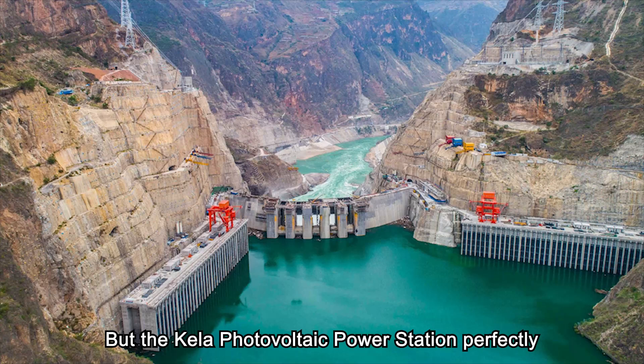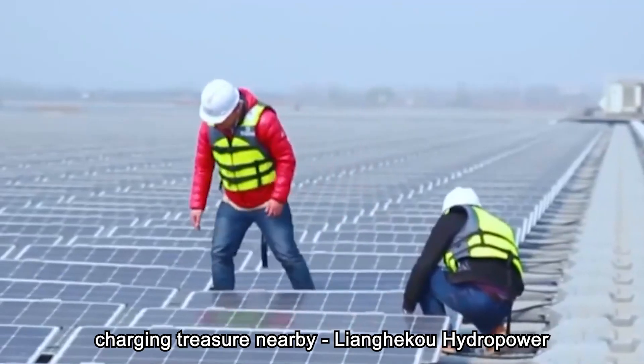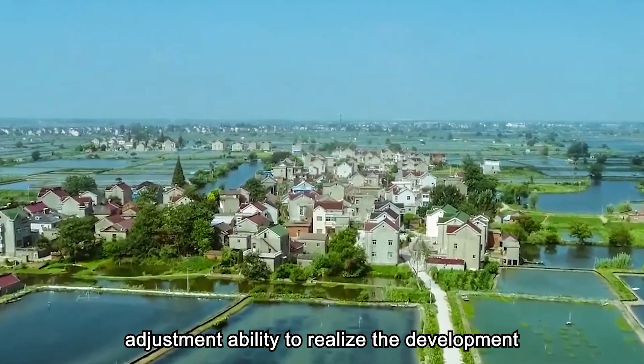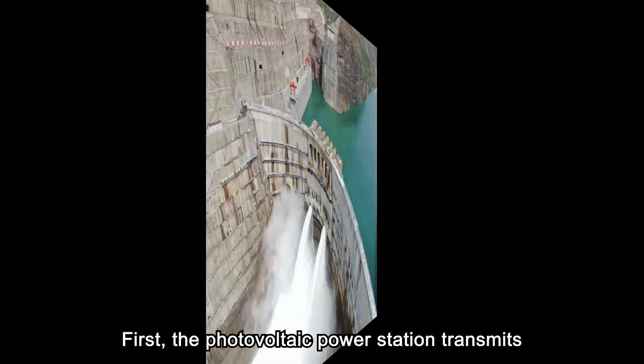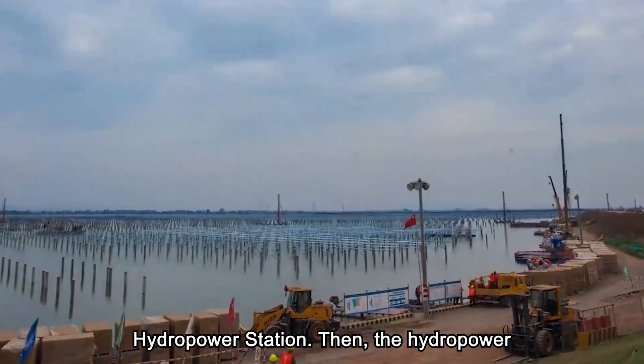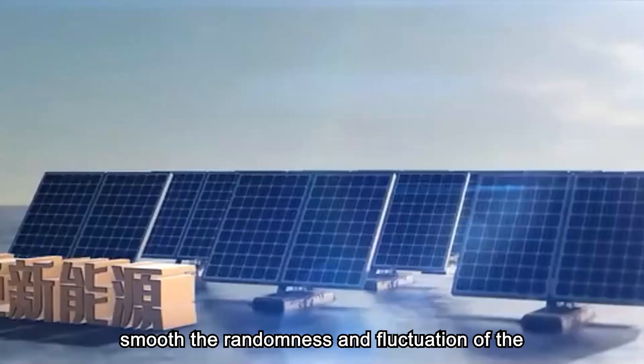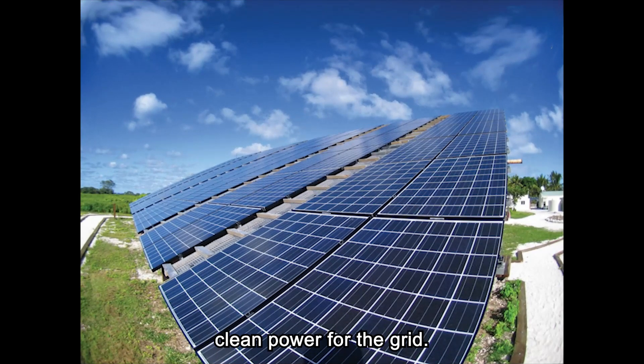The Kela Photovoltaic Power Station perfectly solves this problem, because there is a nearby Lianghekou Hydropower Station. This hydropower station with an installed capacity of 3 million kilowatts can use its unique adjustment ability to realize water-solar complementarity. The photovoltaic power station transmits its electricity to the Lianghekou Hydropower Station and becomes a virtual unit of this hydropower station. The hydropower station then uses its powerful adjustment ability to smooth the randomness and fluctuation of photovoltaic power, providing stable, high-quality clean power for the grid.